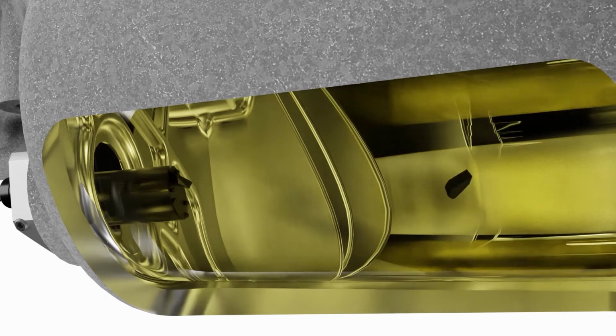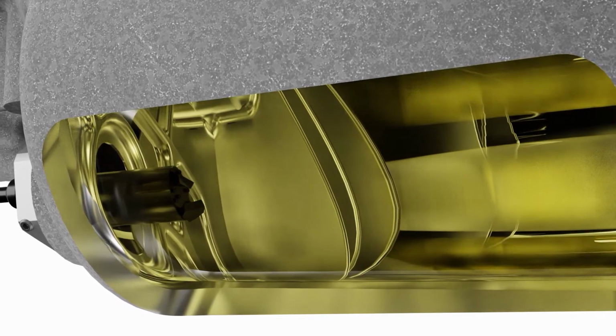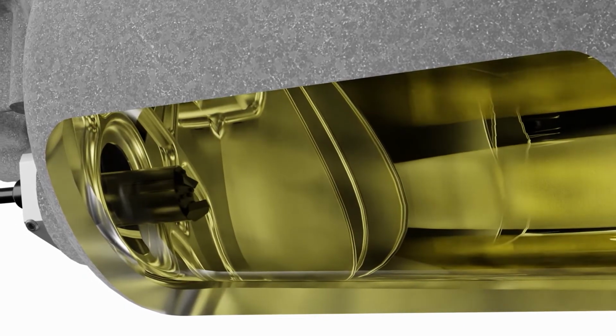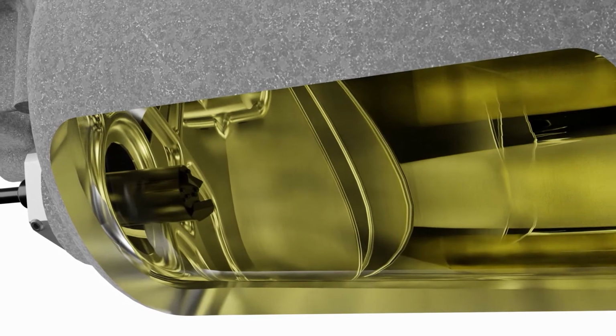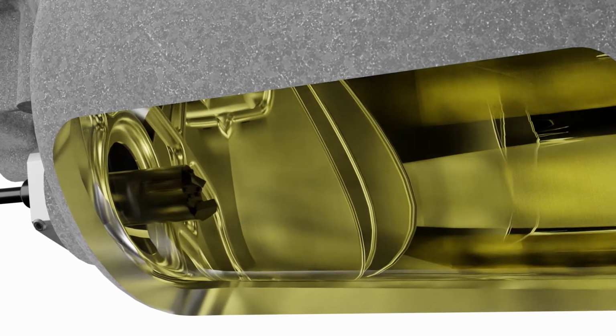The high-power neodymium iron boron permanent magnet is the strongest commercially available grade and will grab particles of any size and trap them on the surface of the sensor probe face.